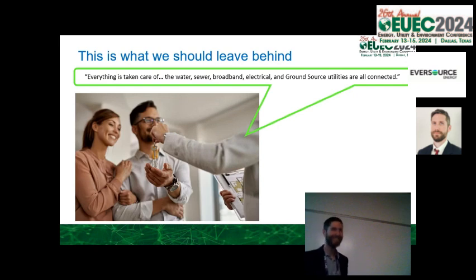I'm working on it. Question is the heat pump itself, what are the limits as far as temperature? We can operate a ground source heat pump with 28-degree water. We can heat a building. And when we get to around 105 degrees, we start to run out of ability to cool a building. So that's the source water. But as far as making heat, 120-degree water is easy, standard. That's what we do. And 100-degree air and 50-degree air is kind of normal. And you can always step it up beyond that if you have, say, a cafeteria where you have to have the water temperature higher.